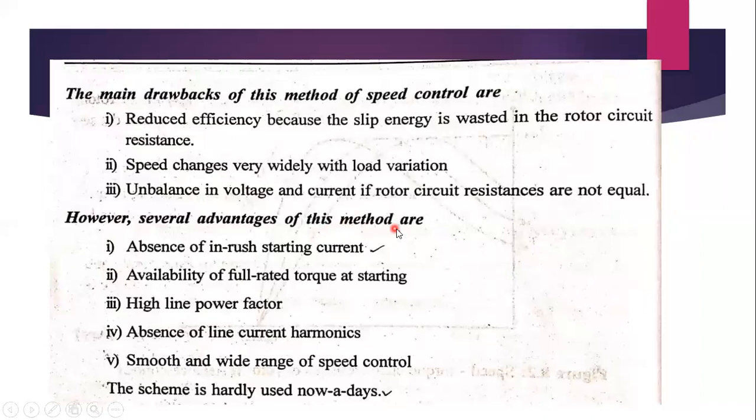However, there are several advantages of this method. One is the absence of inrush starting current. Inrush starting current means high starting current, which can be reduced by using this method. Next, full rated torque is available at starting, that is, high starting torque. So the starting current is less and the starting torque is more.